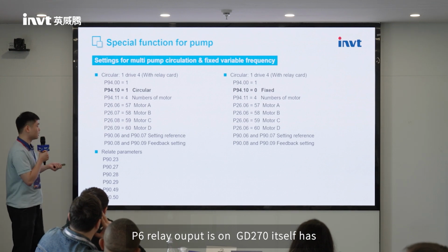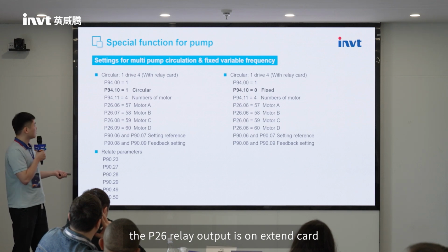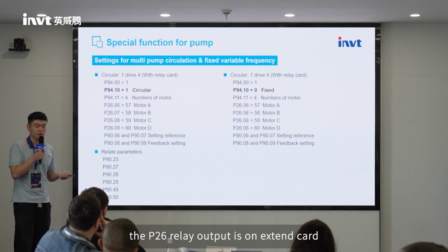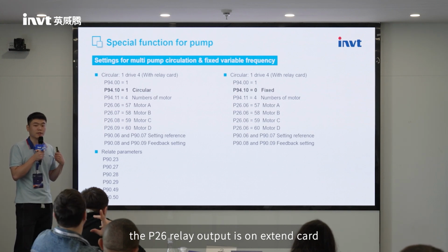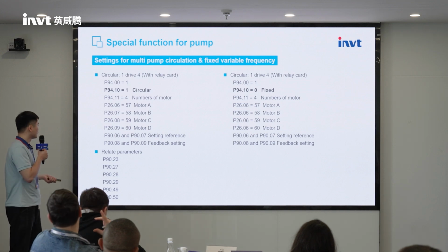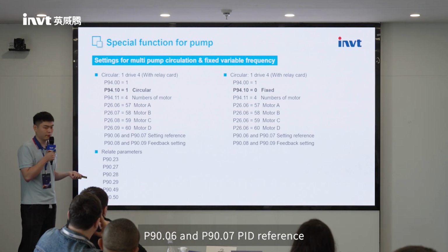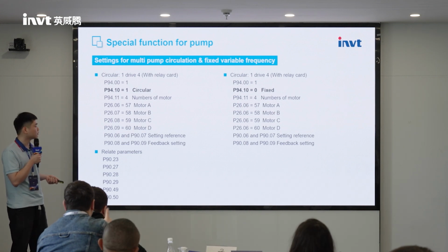P6 is the one the GD270 itself has. The P26 is related with the IO expander card. P90.06 and P90.07 are the PID reference setting, and P90.08 and P90.09 are the PID feedback setting.